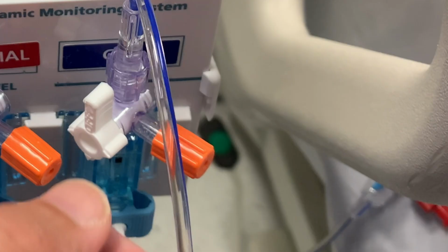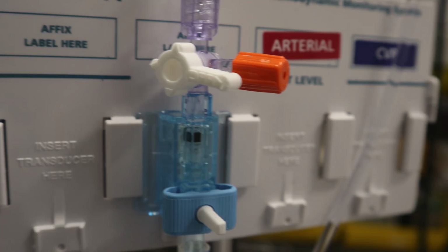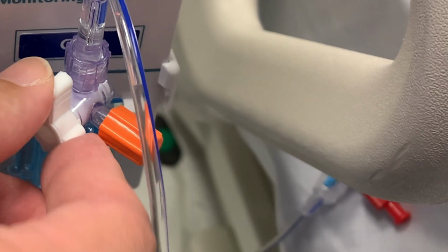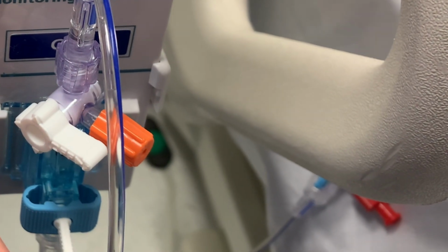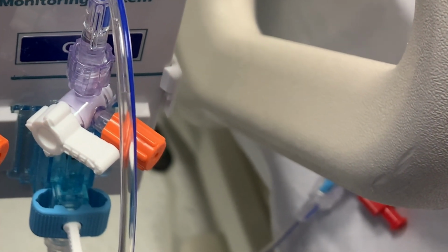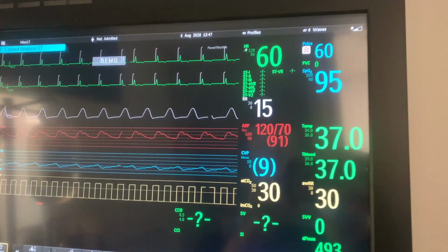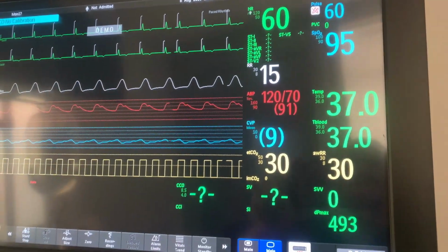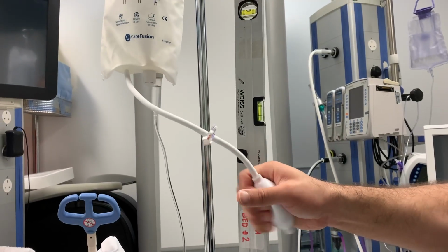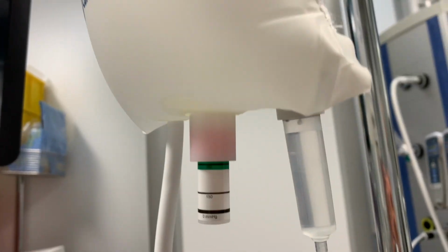Place a new sterile injectable or non-injectable cap on the stopcock. Now, as I told you previously, in this model, no need to change the stopcock. This is from the manufacturer. Turn the stopcock so that it's open between the patient and the transducer. Now observe the waveform. You need to check the IV pressure bag every 4 hours or as needed. Maintain it at 300 mmHg.